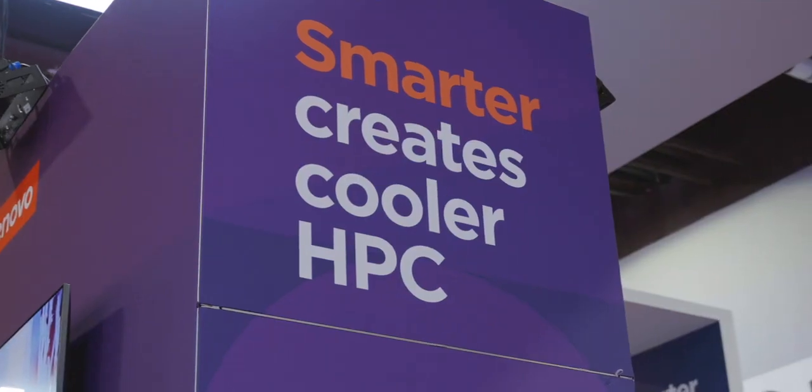When you look at the booth, we have a lot of AI systems, like an 8U that is 100% air-cooled today, but we have the same systems as water-cooled, where we just cool the core components, in this case CPU, GPU, DIMMs, and we are also now looking at PCIe adapters as they are getting hotter and hotter and consuming more wattage. So we really bring our high-end water cooling technology into the whole portfolio, supporting those systems with heat to water. That makes a huge step in sustainability. With chips getting hotter and hotter, you likely waste 20 to 30% of all the electricity in cooling, just for fans and cooling the room. So that's a great step forward, where we can now use the technology we had before in all of our systems.